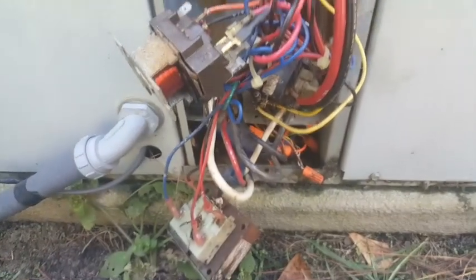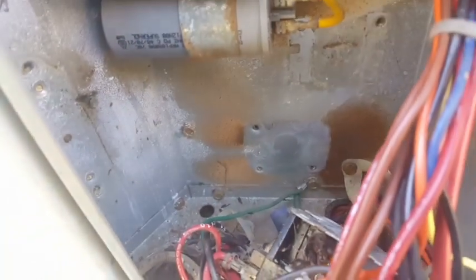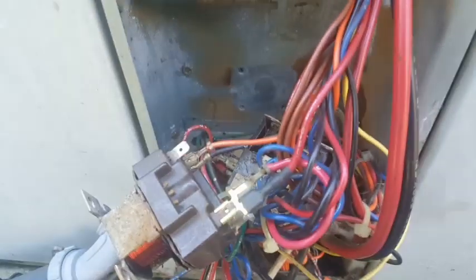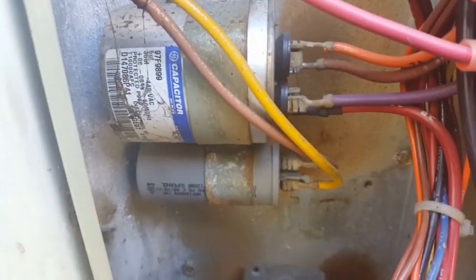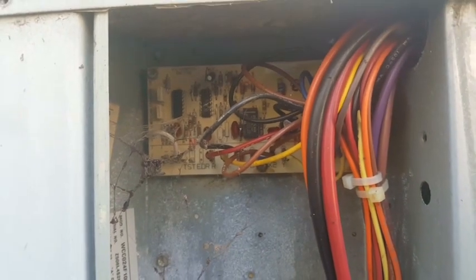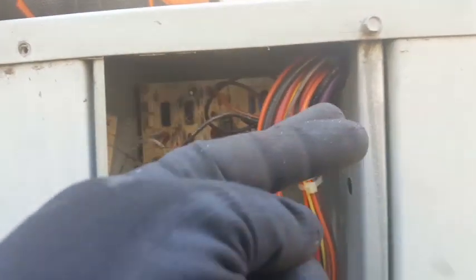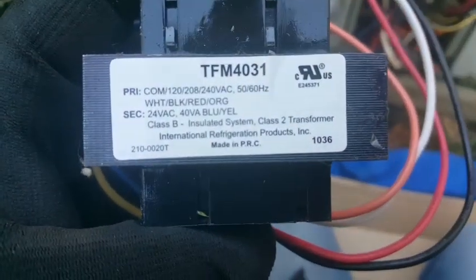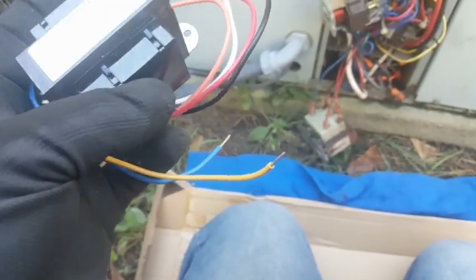Sexy. I got some of our parts disconnected, wiring still connected. I'm going to go through and install the new parts there: transformer, double pole, double throw relay, and contactor. And we'll just put the wires one by one back in place and move these old parts out of the way. After those, I'll move on to the capacitors there, get them switched out as well. Now, hopefully our defrost board won't give us any trouble. Fingers crossed. This is our new transformer. You can see we'll be using white and orange because we have 240 volts AC. And we'll just wire out the other two off. These are our low voltage.